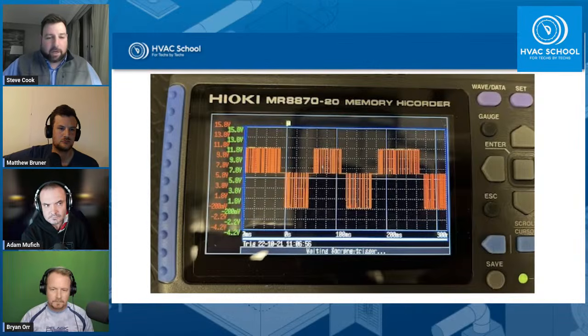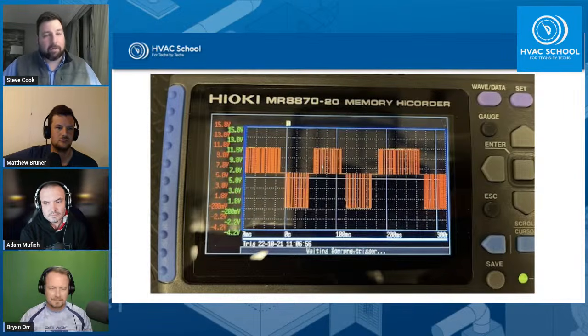When you come across communication systems that aren't doing anything, and you've replaced boards and done all this - it's amazing how many times this happened during my time at Mitsubishi. You come across systems pulled in with solid core wire that ran fine for years and now suddenly don't. The final fix was replacing the wire. I know it sounds difficult and like a lot of work, but I guarantee it will likely fix your communication issue if you don't have a fault code.